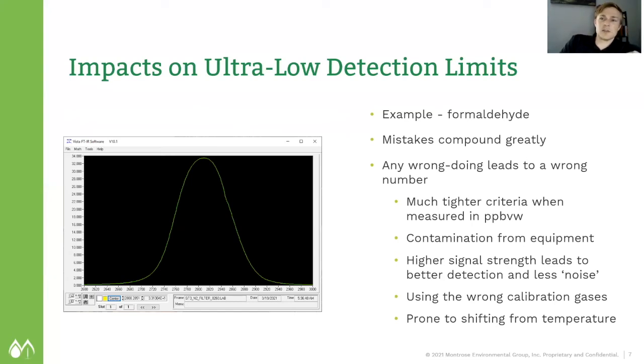Now, if that single beam drops during testing, whether it's from particulate, from temperature swings, whatever it may be, it's going to impact your data. You might be thinking that you're seeing 10 ppb formaldehyde, but in all reality, it might be higher, it might be lower. In order to know, you need to validate the data.